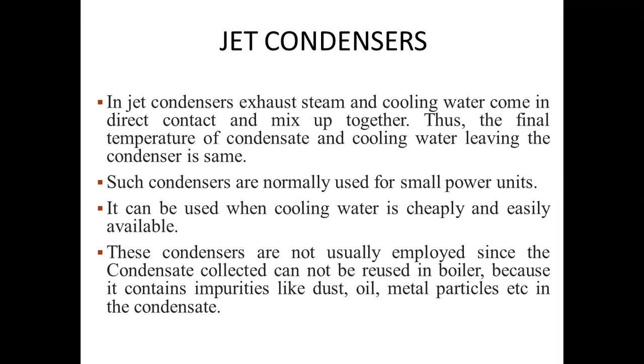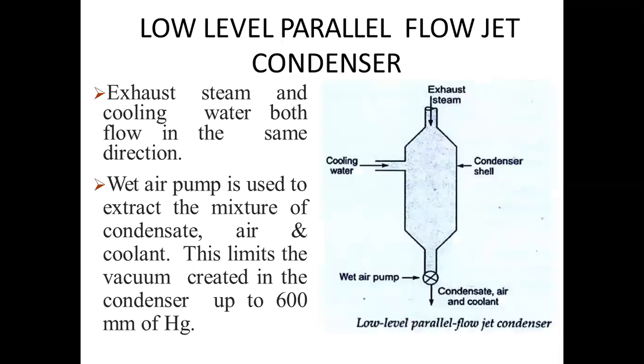Thus, the final temperature of the condensate and the cooling water leaving the condenser is the same. This type of condenser is generally used for small power plants, and when cooling water is very cheap and easily available. These condensers are not usually employed since the condensate collected cannot be reused for the boiler, because it contains some impurities like dust, oil, metal particles, salts, etc. in the condensate itself.